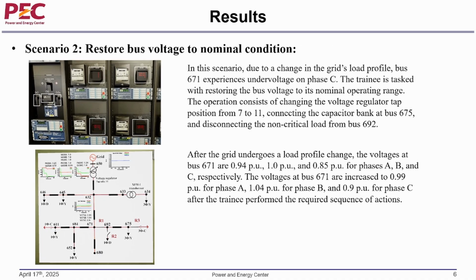For the second scenario, the trainee needs to restore the bus voltage to its nominal condition. In this scenario, due to a change in the grid load profile, bus 671 experienced an undervoltage on phase C. This here shows the bus voltage, the graph, and as well as this meter show the bus 671 voltage. The trainee is tasked with restoring the bus voltage to its nominal condition. The operation consists of changing the voltage regulator tap from 7 to 11, connecting the capacitor bank at bus 675, and disconnecting the non-critical loads at bus 692.